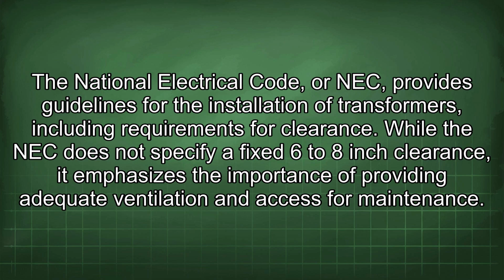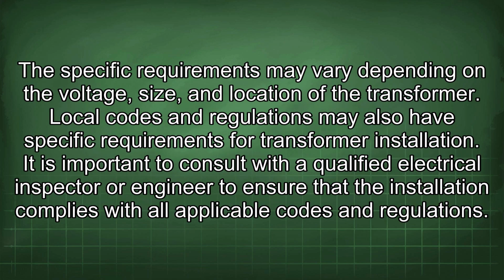The National Electrical Code, or NEC, provides guidelines for the installation of transformers, including requirements for clearance. While the NEC does not specify a fixed 6 to 8 inch clearance, it emphasizes the importance of providing adequate ventilation and access for maintenance. The specific requirements may vary depending on the voltage, size, and location of the transformer. Local codes and regulations may also have specific requirements for transformer installation. It is important to consult with a qualified electrical inspector or engineer to ensure that the installation complies with all applicable codes and regulations.